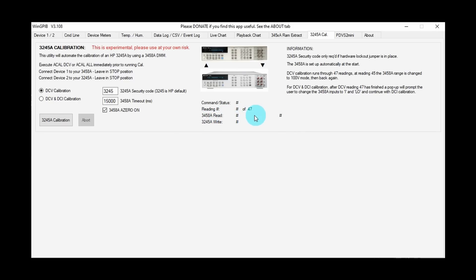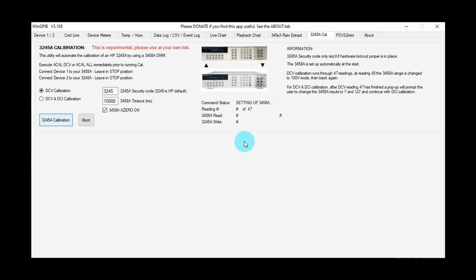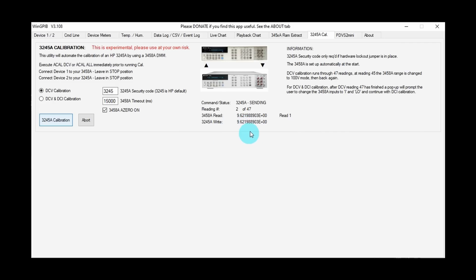So we're all ready to go. Let's just hit the button. And we're starting the tests, setting up 3458A. I heard the relays click in the unit, and we're off and running. As you can see, the 3245A is sending various voltages to the 3458A. So we'll just leave that run—should take about 10 to 15 minutes, something like that.